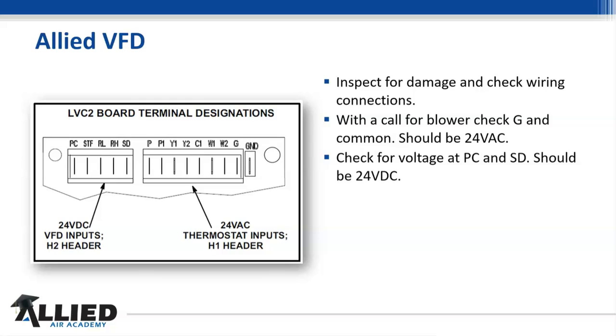Now let's check for voltage on the PC and the SD, and we should see 24 volts DC. It's going to start converting and sending signals to that drive in order to tell it what to run. Because when you get a Y1 and a Y2 call on a multiple system, that DC voltage is going to change. Where you saw the 10 volt DC, it's going to come from these 24 DC outputs on the number 2 header, okay? So we need to check for those voltages there. We got 24 volts in, we got 24 volts DC coming out. We're getting pretty close to saying our board's good to go.